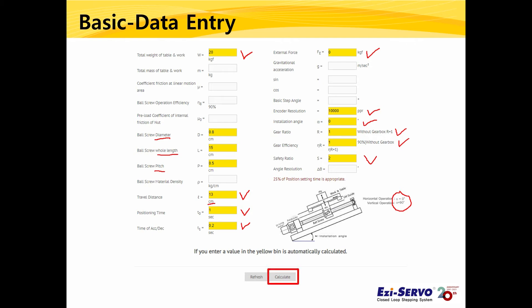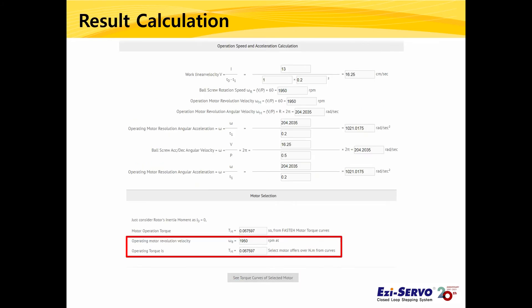When you finish entering the data and click Calculate, the calculated result is displayed on the screen. The values we need to check are the rotation speed and operating torque of the motor at the bottom of the motor selection section. As calculated in this example, we need a motor that can produce torque larger than 0.067 Nm at 1950 rpm.